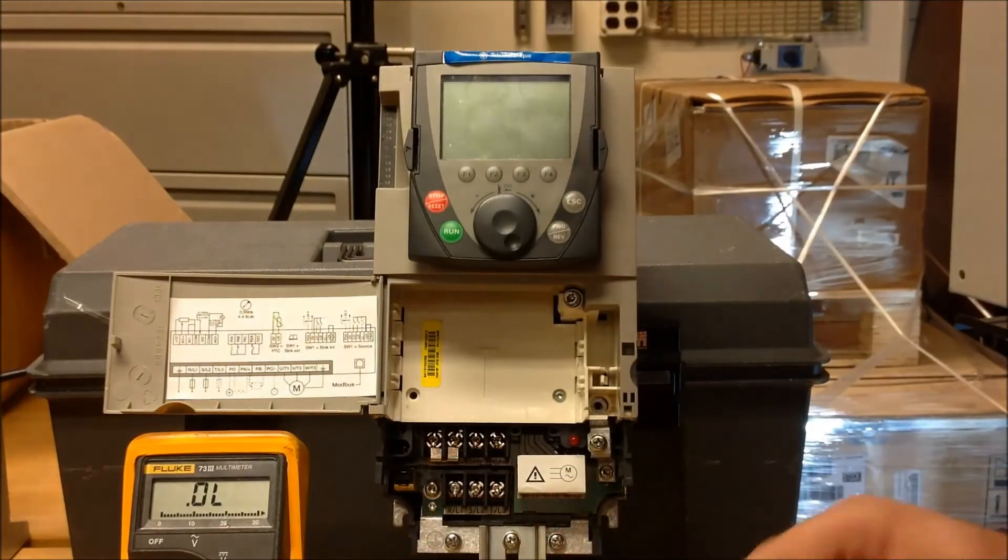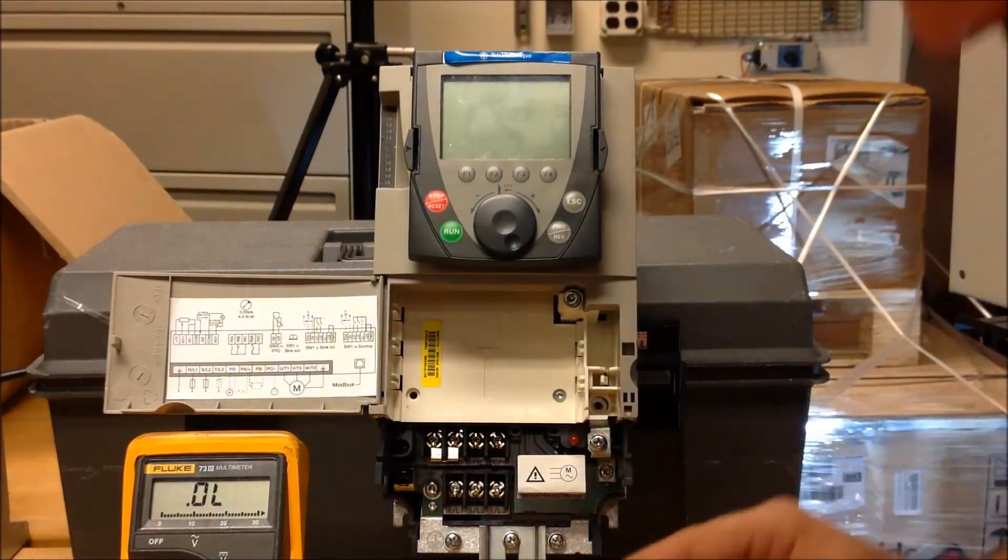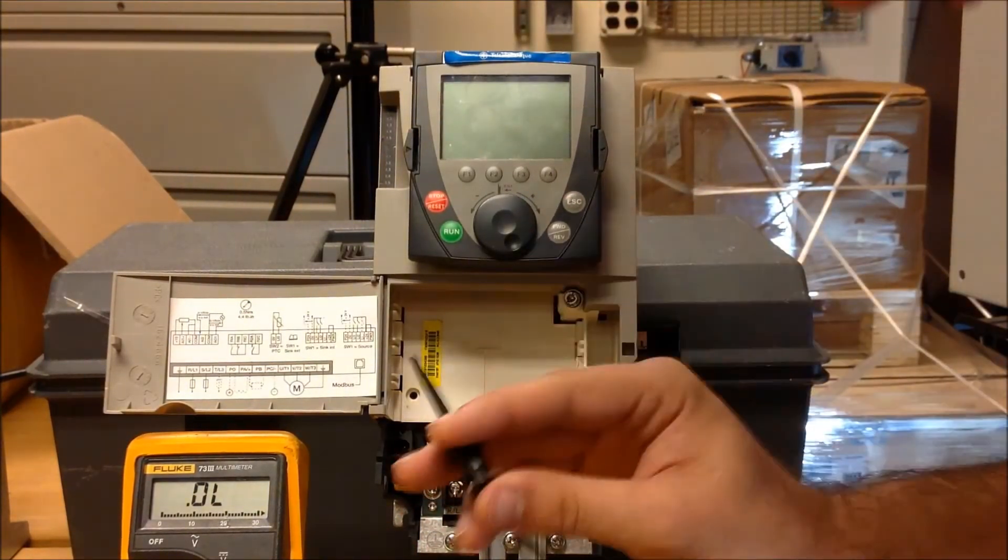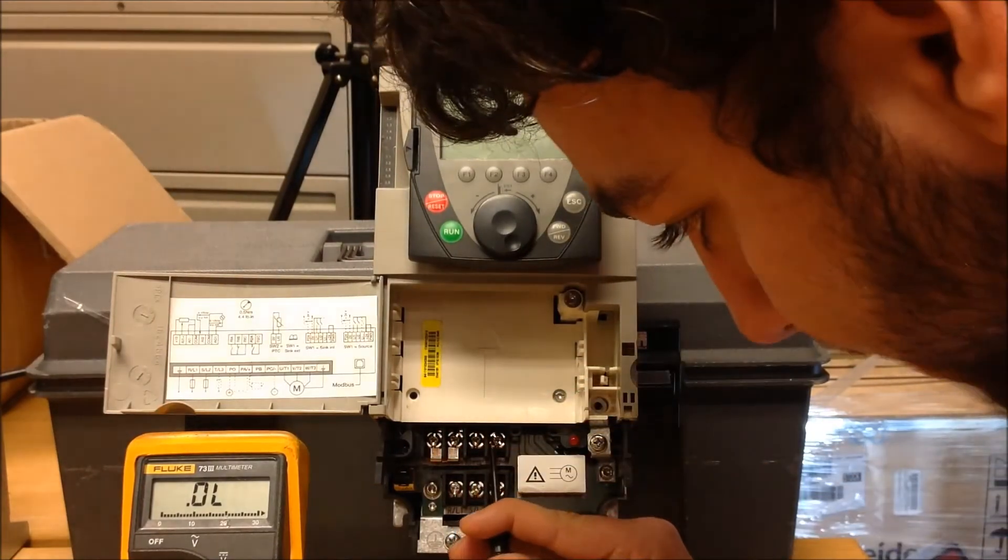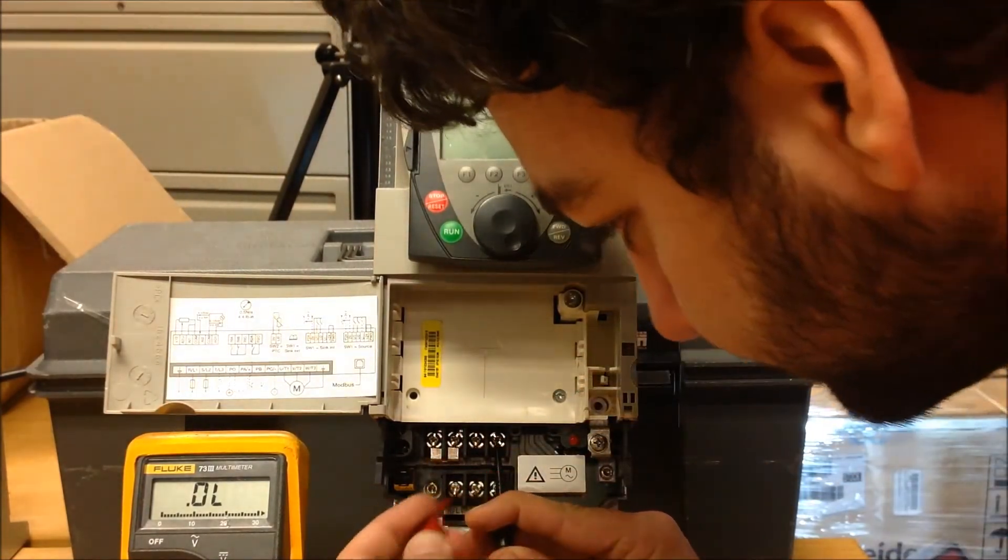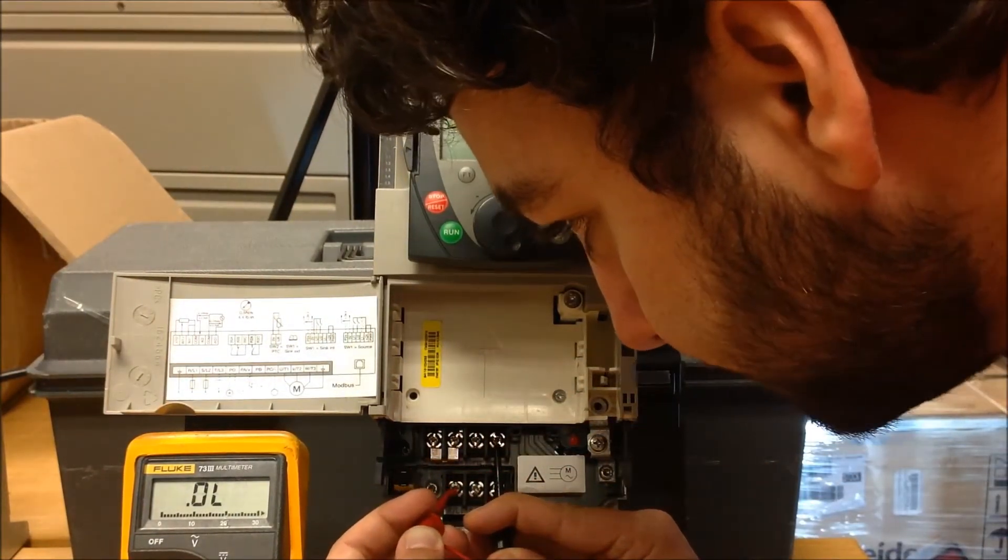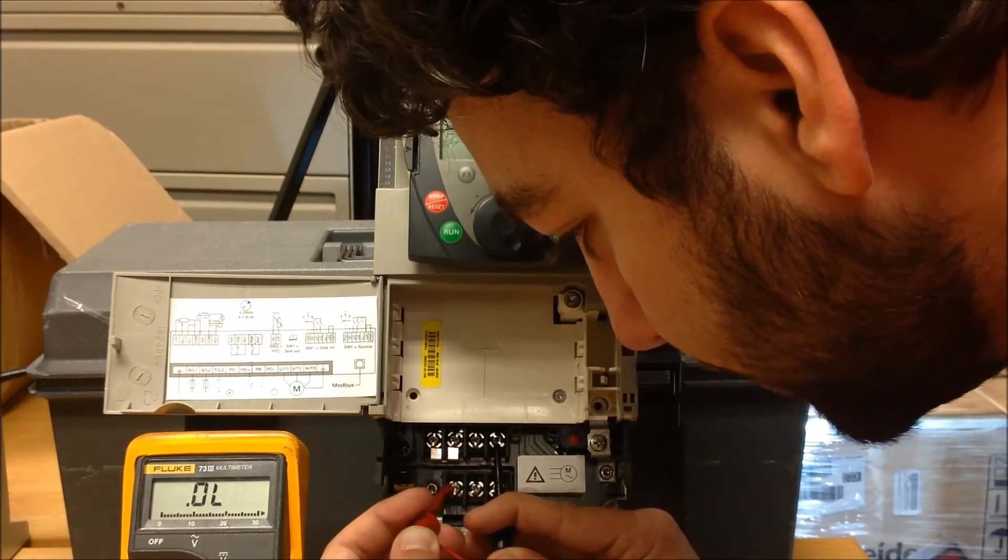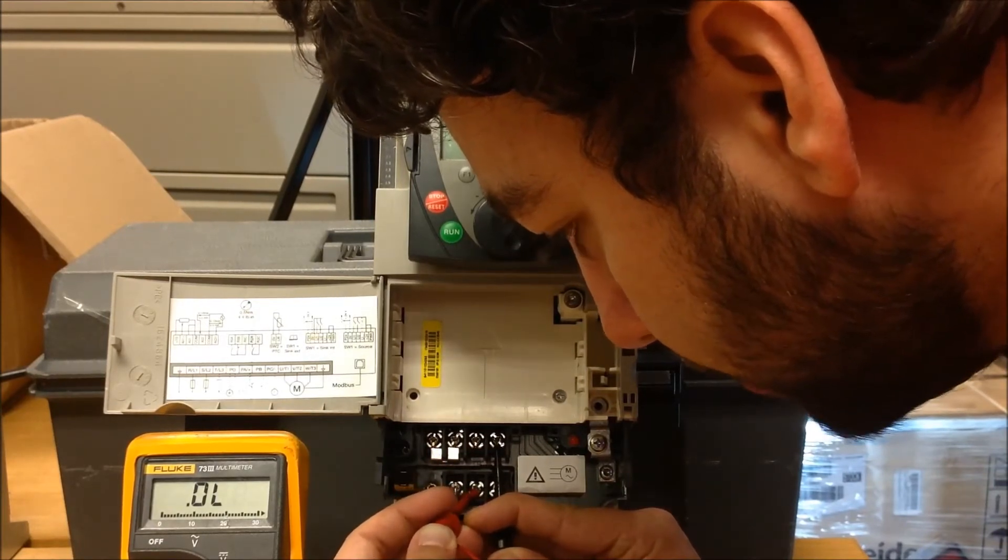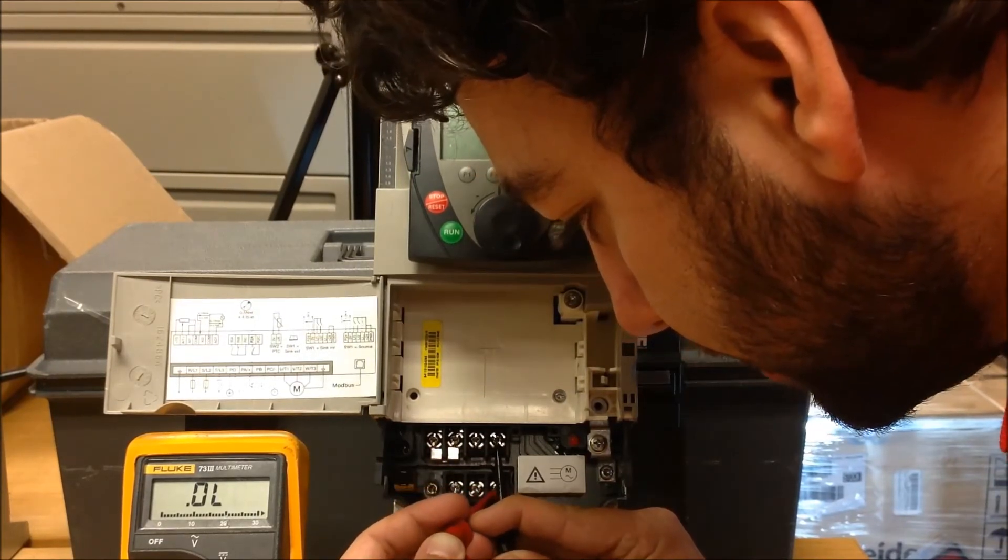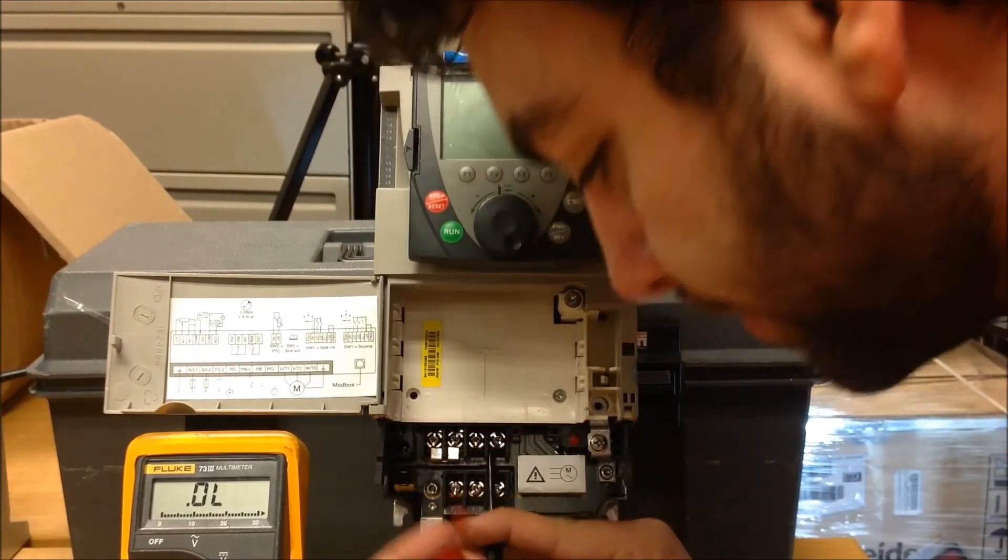Now, one last test. Swap your leads one more time, this time with your negative side of your meter to the DC minus. Same measurements. L1, overload. L2, overload. And L3, overload.